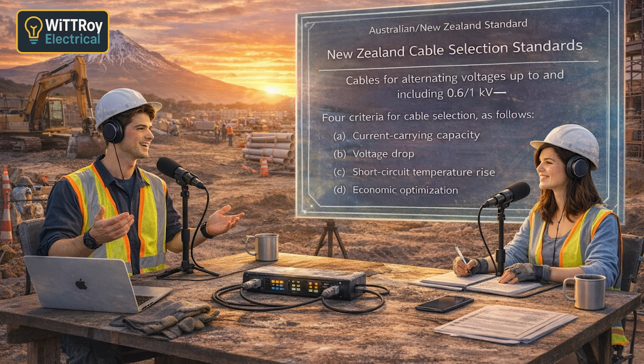Yes. So what about insulation? Insulation traps heat. So heat can't escape. Correct. So current capacity drops again. And temperature. Higher ambient temperature means less cooling. So again, lower capacity. Exactly. So basically, everything that makes it hotter reduces capacity. Perfect. So after applying all these factors, we get the real current capacity. Yes, and then we choose a cable size that meets that. Okay, so that's current sorted.